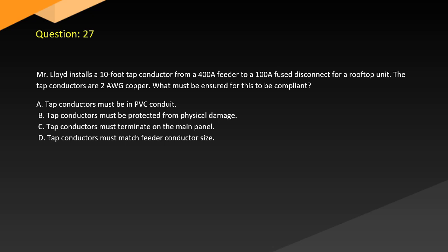Question 27. An installer installs a 10-foot tap conductor from a 400-amp feeder to a 100-amp fused disconnect for a rooftop unit. The tap conductors are number 2 copper. What must be ensured for this to be compliant? A. Tap conductors must be in PVC conduit. B. Tap conductors must be protected from physical damage. C. Tap conductors must terminate on the main panel. D. Tap conductors must match feeder conductor size.